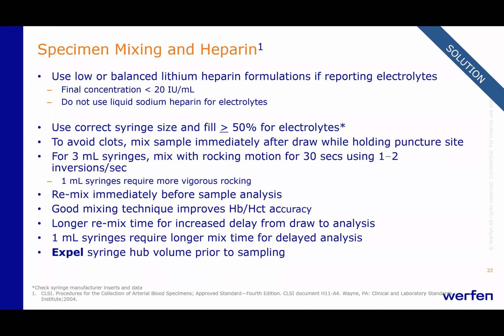To avoid clots, mix a sample immediately after the draw while holding the puncture site. Again, do not set the syringe down because microclots, as noted, can start to form within 10 seconds. For a 3 ml syringe, the recommended mixing is to use a rocking motion for 30 seconds using 1 to 2 inversions per second. And that will adequately mix the heparin with the sample. It's immediate and at least 30 seconds of rocking to adequately mix the heparin with the sample to prevent microclot formation. 1 ml syringes don't mix as well, so they may require a longer and more vigorous rocking.